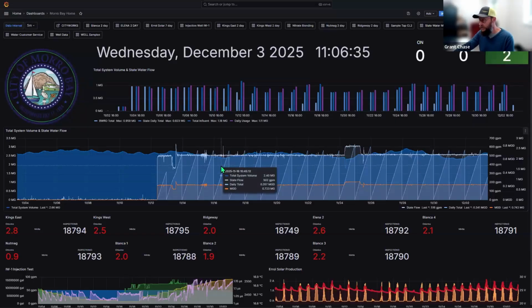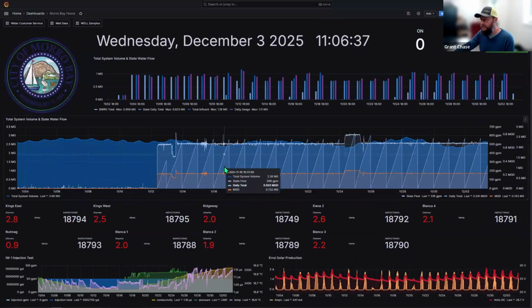Down below, we have total system volumes and influent flow, as well as daily totalizers over that same 30-day window. Below that, we have samples of chlorine that we take weekly at all of the tanks - this is the most recent sample, and these particular data sources are actually from our CMMS. So we're making API calls to that SaaS offering, that enterprise software, and combining it with process SCADA data all in a single platform, which helps the operations staff only have one place to look.